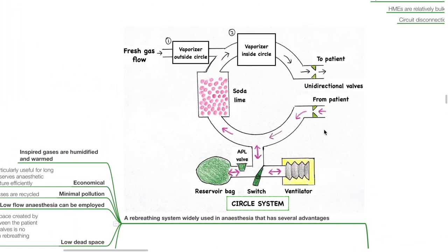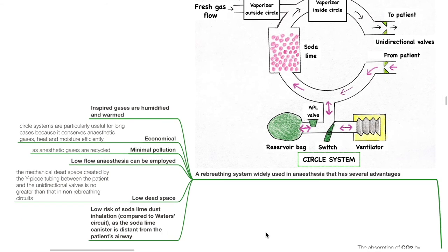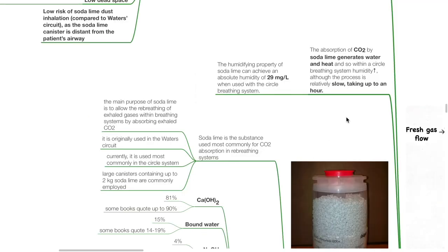Circle systems. This is a rebreathing system that can humidify inspiratory gases and is widely used in anesthesia. Inspired gases are humidified and warm; it is economical as it conserves anesthetic gases, heat and moisture; there is minimal pollution; low-flow anesthesia can be employed; and there is low dead space. The absorption of CO₂ by soda lime generates water and heat, so within a circle breathing system humidity increases with time. Although this process takes up to an hour, the humidifying property of soda lime can achieve an absolute humidity of 29 mg/L when used within the circle breathing system.